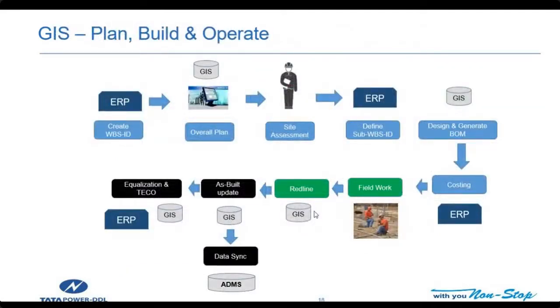Now the typical plan, build and operate process: in the ERP you start by creating a scheme, since every work narrows down to a scheme first. The scheme is created in ERP, for which an overall plan is prepared in the network planning tool using GIS data. After on-site assessment, these schemes are broken down into sub-WBS, and then the design is prepared in a GIS-based system that creates the bill of materials. So GIS is used at two critical junctures, planning and designing. The costing, based on the bill of material generated from GIS, is done in the ERP system.